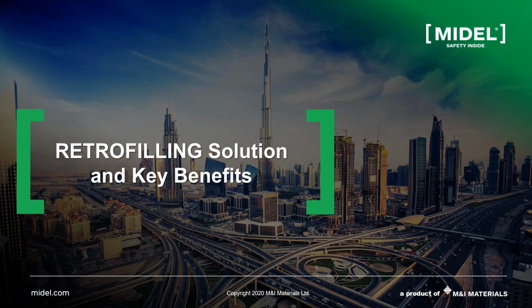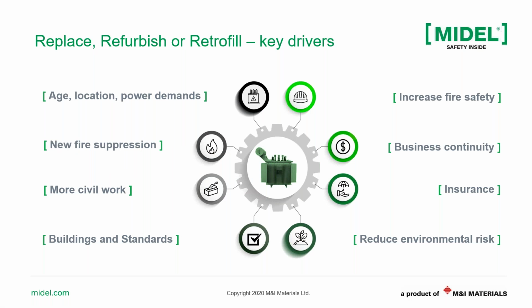End users may end up with a decision, depending on the changing circumstances, either to buy a new transformer or to use other technology like esters to utilize that asset and benefit from the fire safety and biodegradability. So in our grid, we know we sometimes have aging assets, aging transformers, or these transformers are located in sensitive areas, or the power demand is increasing.